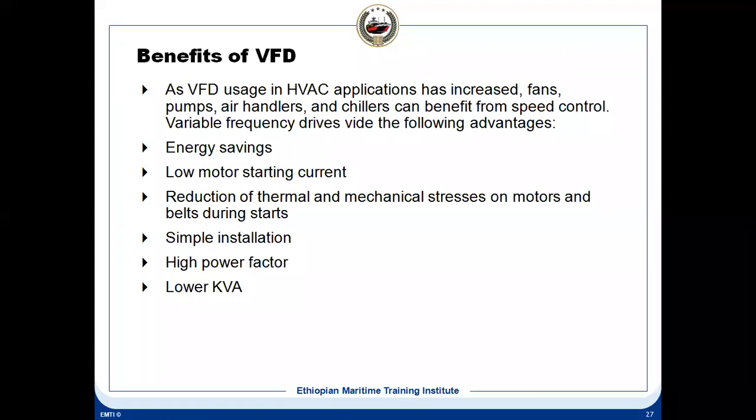Environment impact, energy saving, low motor starting current, smooth starting of a motor, no jerk. Like with a star-delta motor, you have a jerk. When it changes from star to delta, there is a jerk to the motor. Especially with submersible pumps, like in gas ships, LPG and LNG, and oil tankers, you have motors which are submerged. You cannot afford to give a jerk to these motors because it can damage the piping systems. You don't want to give any jerk, so you need a smooth starting in all these places.